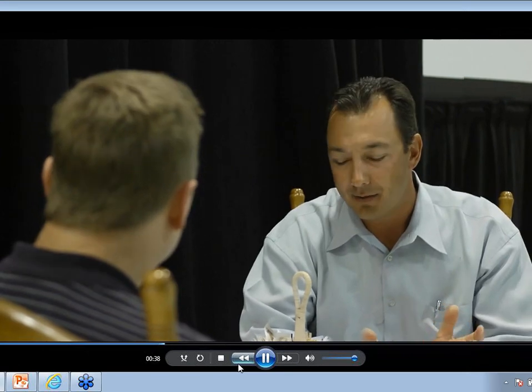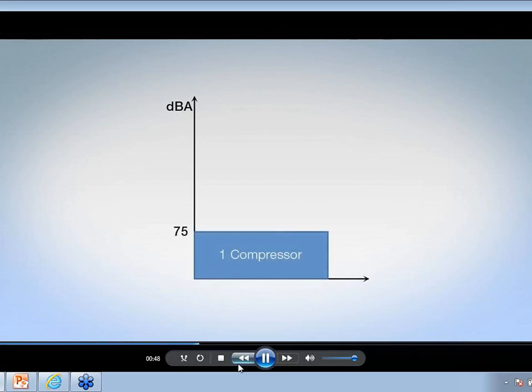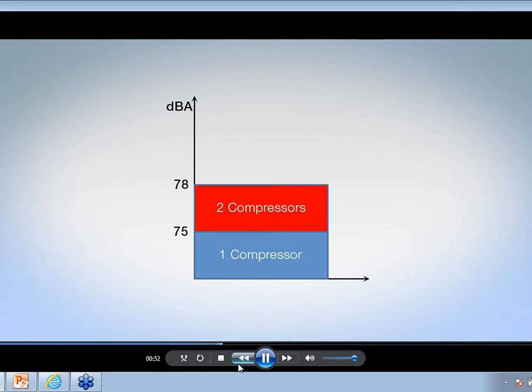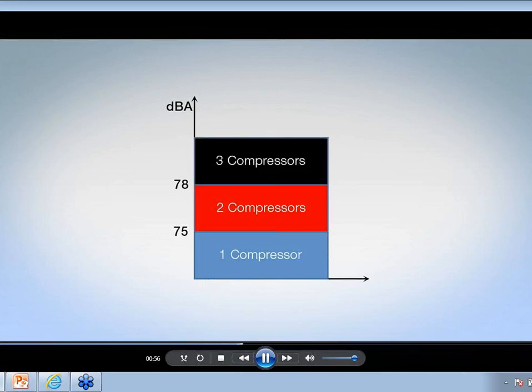Yeah, but that's 3 compressors. So if each is 75 dBA, what do you have with the overall product? Well, I believe with sound in this decibel range, when you add 2 equal sources, then you add 3 dBAs, so that would be 78. Adding a third compressor, you must be close to 80. Why don't they just tell us that? They're charging a great deal for this low sound.